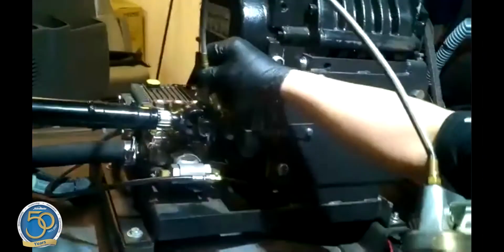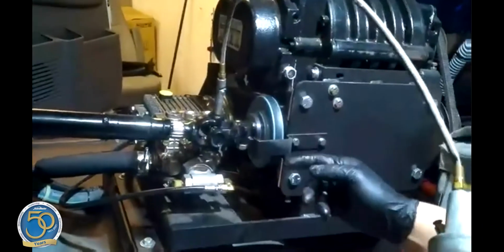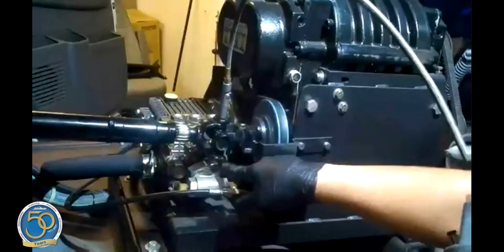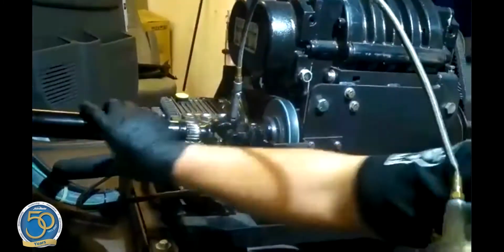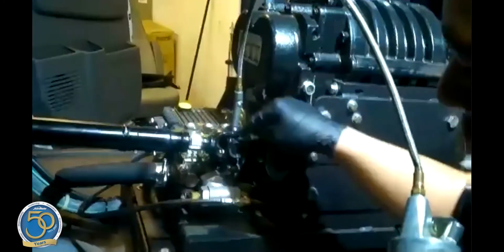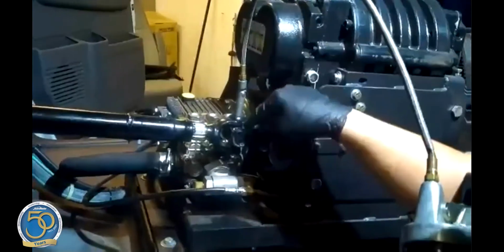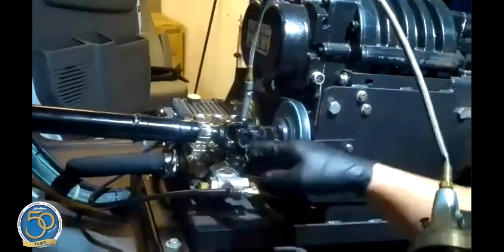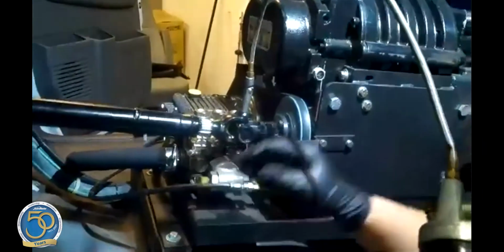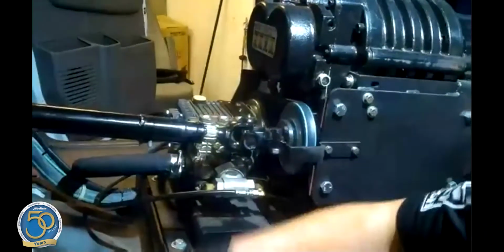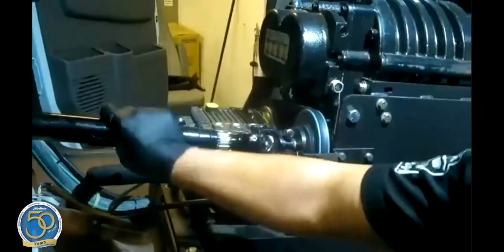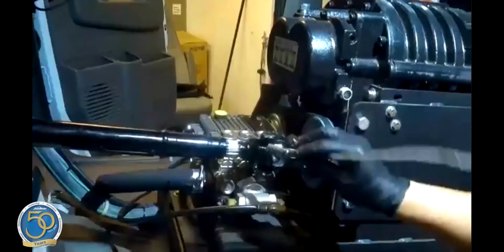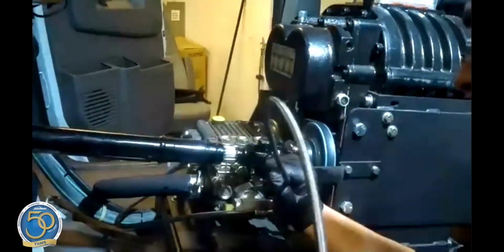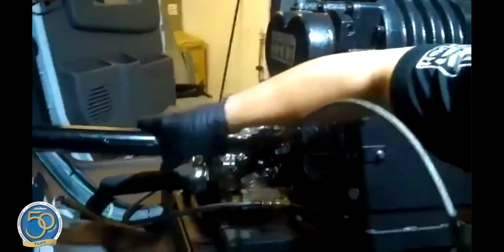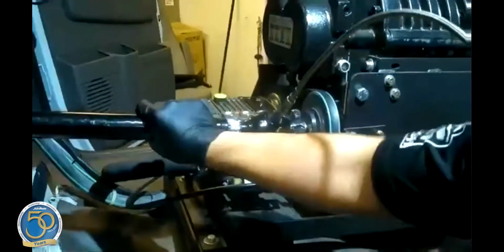I usually pump about one to two pumps in each Zerk fitting. What you want to see is the black grease coming out, and then the new grease coming out, because that's pushing out the old contaminated grease. That's how you know you've properly evacuated the old grease and have the new good stuff in there.